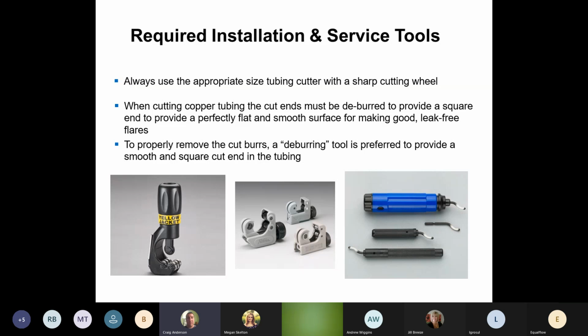Let's deburr it. Let's make sure when we're deburring it, the filings from the deburring tool are not falling in your copper. Always point your copper down. Make sure those filings are falling out. Our TX valves, our EE valves, reversing valves, these all have screens in them. So if we're getting any particles in the system that are blocking off these screens, then it could affect the operation of our air conditioner, especially in a mini split situation. We're dealing with 1/4-inch copper, 3/8 copper. It doesn't take much to block that. So make sure we're deburring it, we're not getting the filings inside the copper, and we have everything proper for cutting tools and stuff.